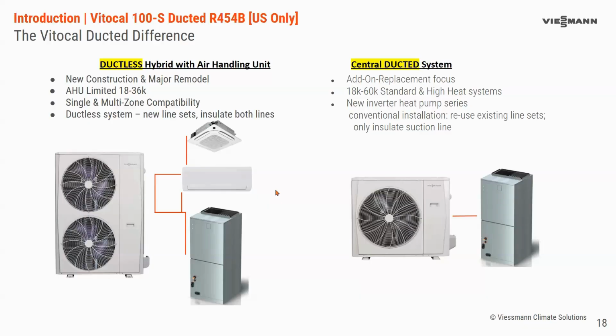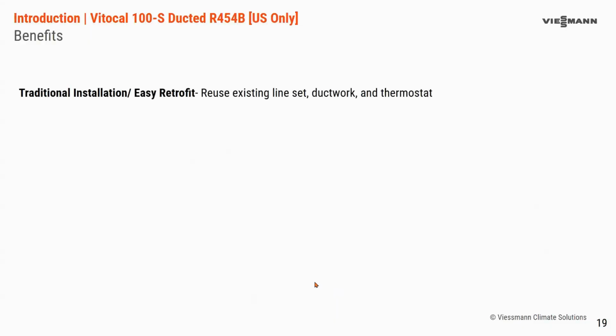You would also need new line sets for that smaller diameter, and you have a requirement to insulate both line sets. The central ducted, you go up to 5 ton, and you have the ability to reuse your line sets, and you only need to insulate the suction line. So if you have a system that's already existing and the suction lines are already insulated only, this is going to be your ideal lineup here. So if you have a ducted dedicated system, this is the one for you. If you want to do a hybrid, then you can go into the ductless option as well.